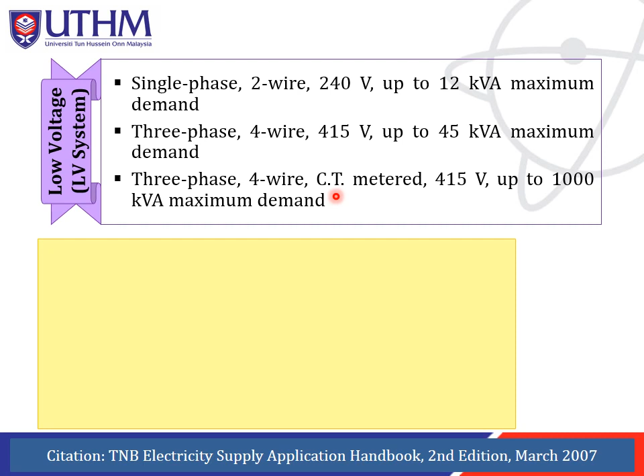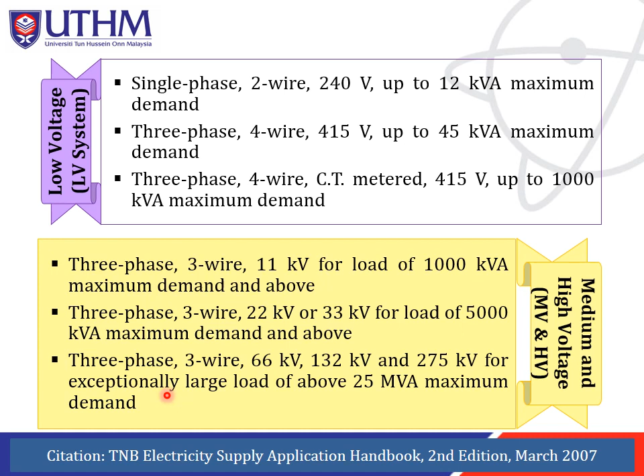Meanwhile, for medium and high voltage, it can be 3-phase, 3-wire, 11 kV for loads of 1000 kVA maximum demand and above, or 3-phase, 3-wire, 22 or 33 kV for loads of 5000 kVA maximum demand and above, or 3-phase, 3-wire, 66 kV, 132 kV and 275 kV for exceptionally large loads of above 25 MVA maximum demand.